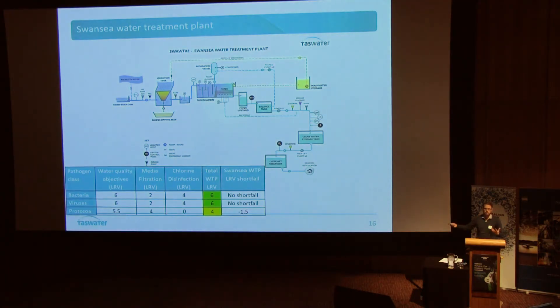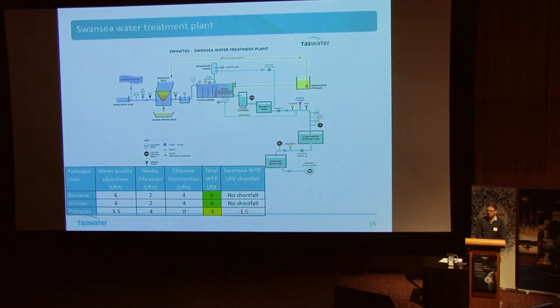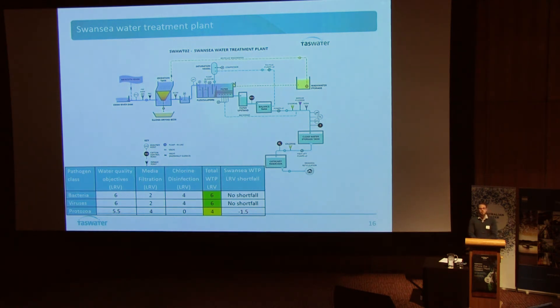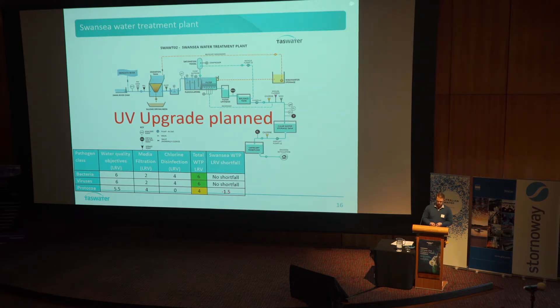So knowing we were in category four, we then looked at the Swansea water treatment plant to assess what we have that can mitigate pathogen risk. Category four means you need 6-log virus removal, 6-log bacteria removal, and 5.5-log protozoa removal. The processes at Swansea are media filtration and chlorine disinfection. We're hitting our bacteria and virus objectives, but we have a shortfall on protozoa. So we have a project now to install a UV disinfection unit at the site so that we meet our water quality objectives.